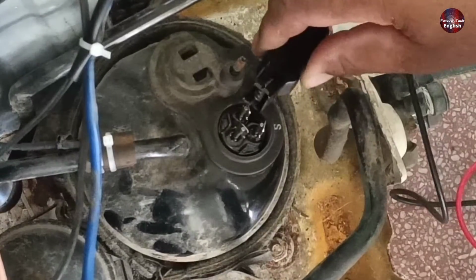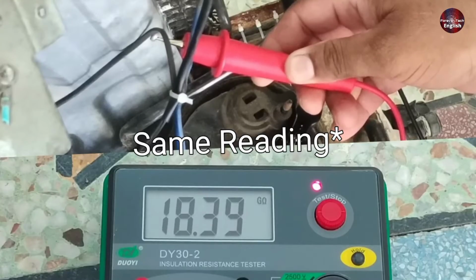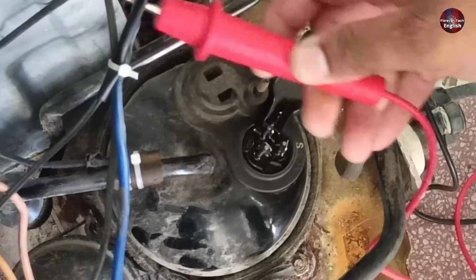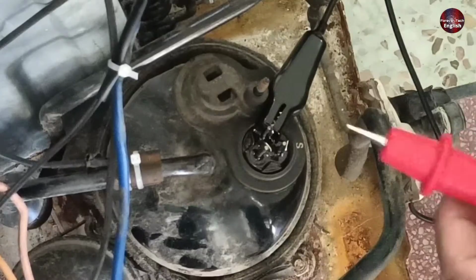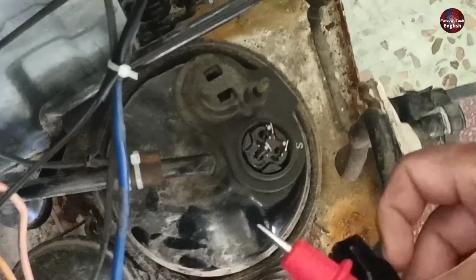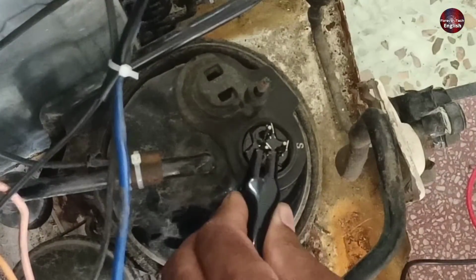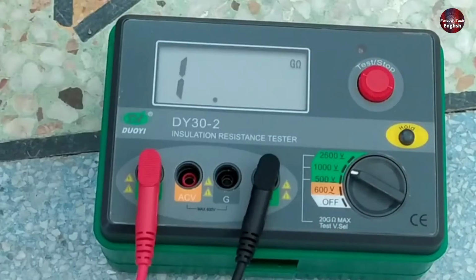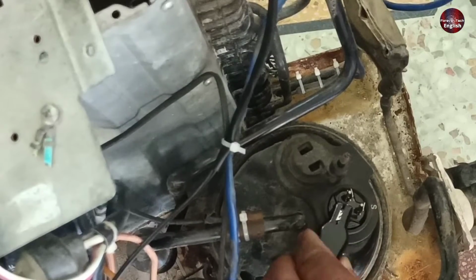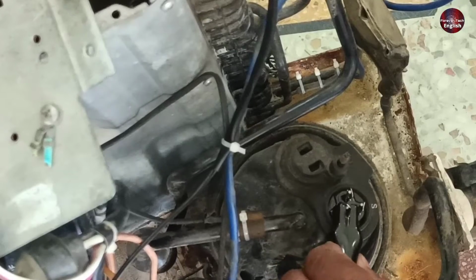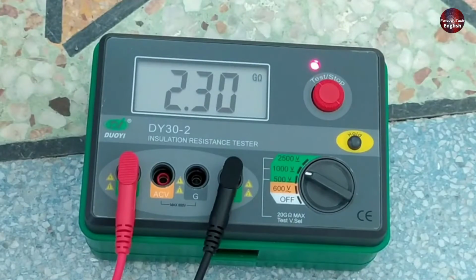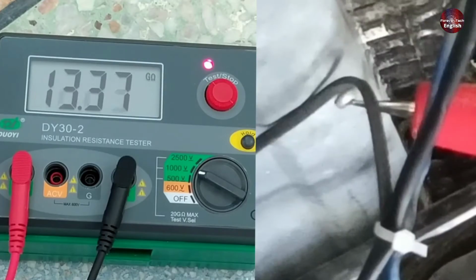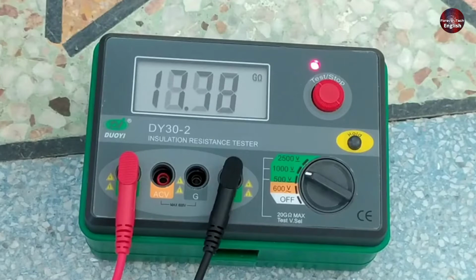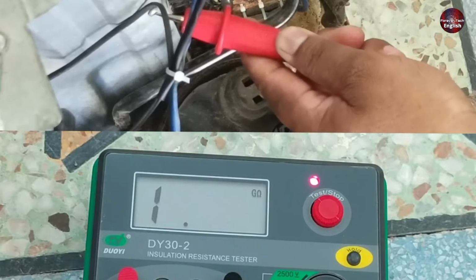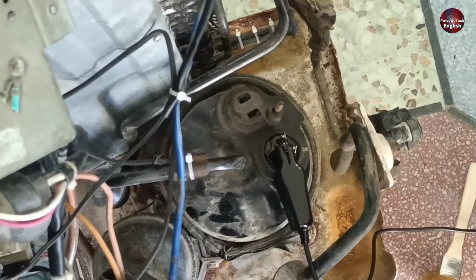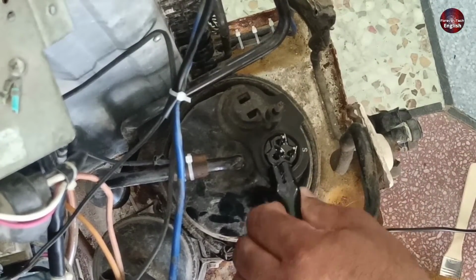Now, let's check with the second terminal. The tester is already set on the test mode in the same reading. But again, avoid touching the probes of the tester. Press the button to stop the tester. And check the compressor with the third terminal. Now again, I will press the start button by attaching the probe to the body. We are getting the same reading on the insulation tester as well. Now after testing all the terminals, it means all the compressor terminal winding is okay.